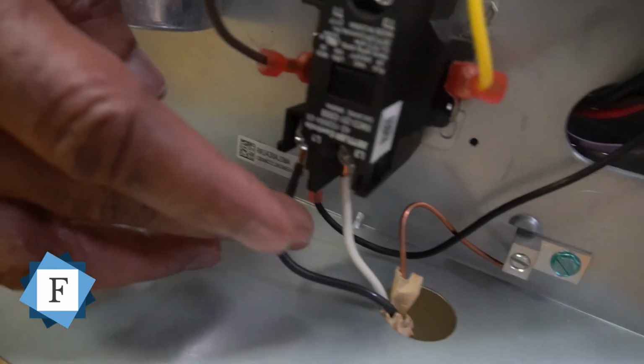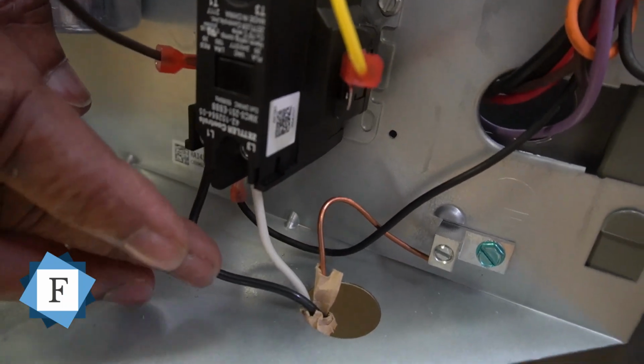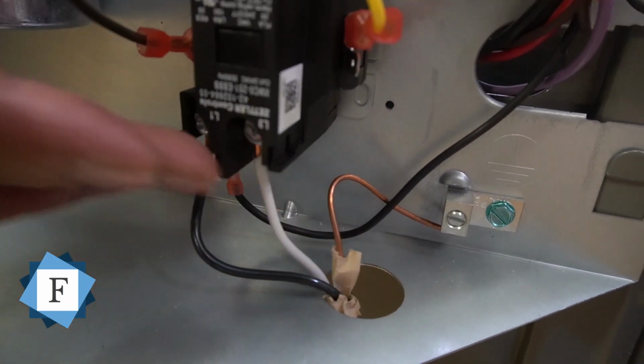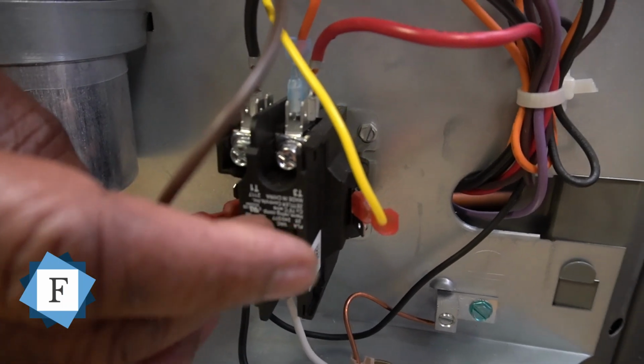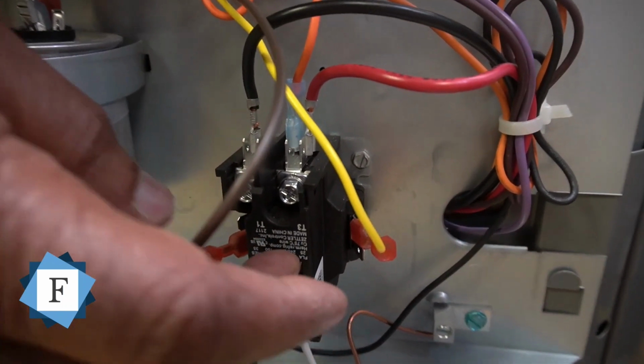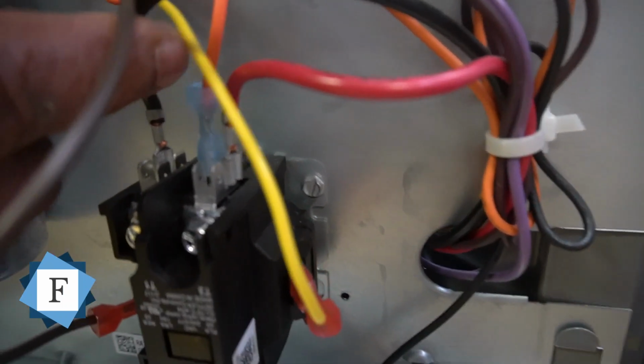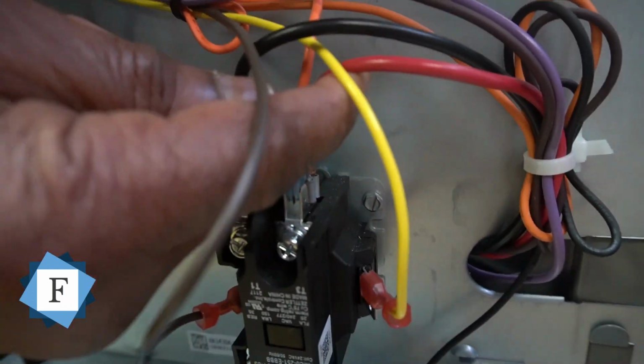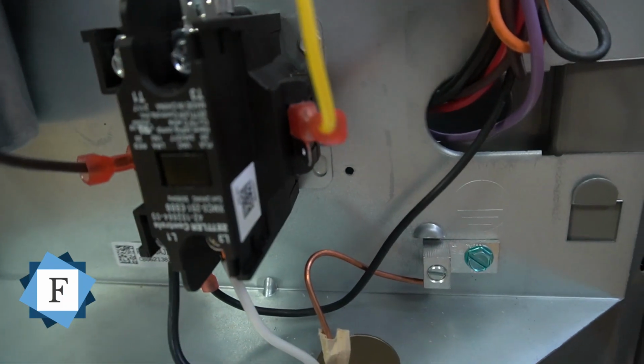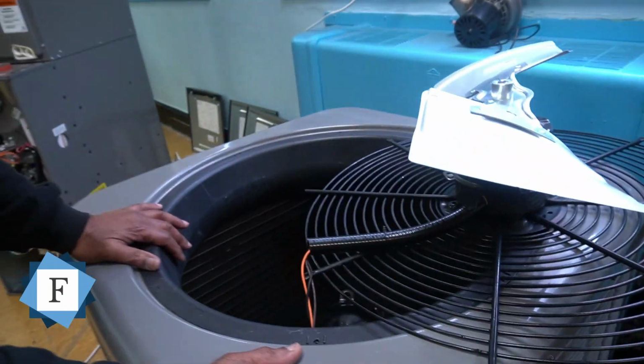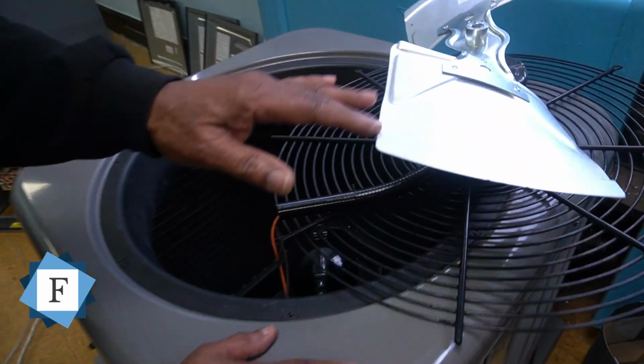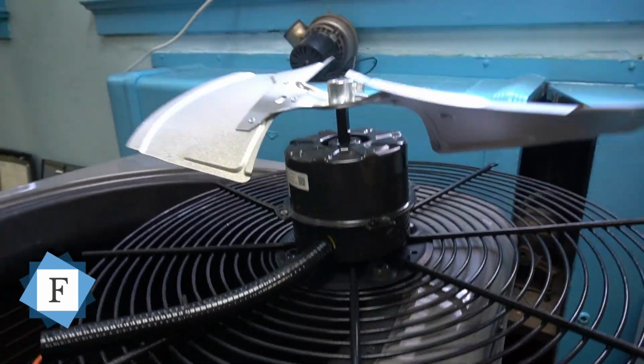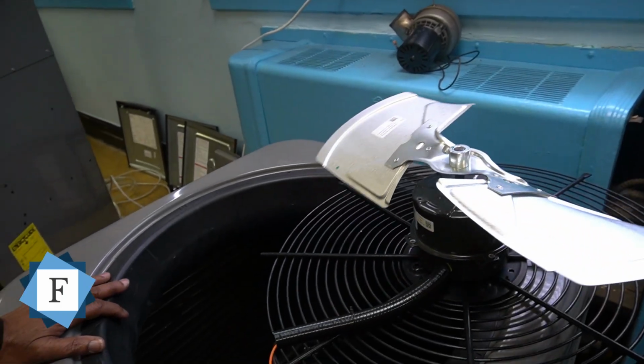Each leg is 120 volts, so that gives us 240 volts coming in, and if we have 24 volts and this contact is pushed in, that means we have 240 volts going out at the top. Now, the 240 volts is enabling the compressor and the condenser fan to come on. They're 240 volts. That's what's happening with the 240 volts.